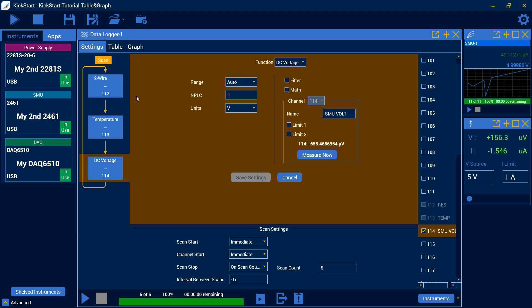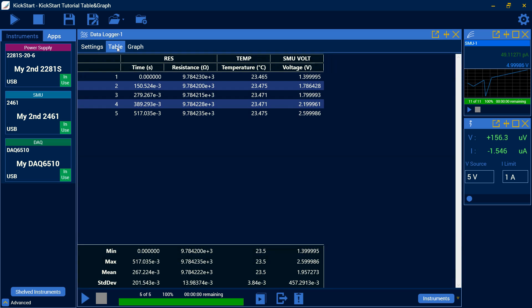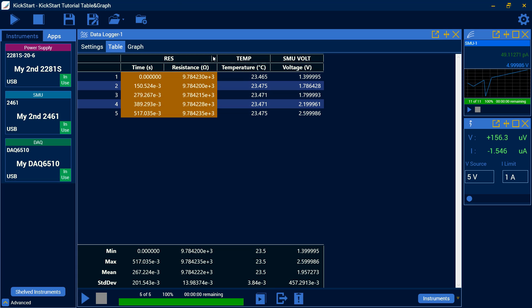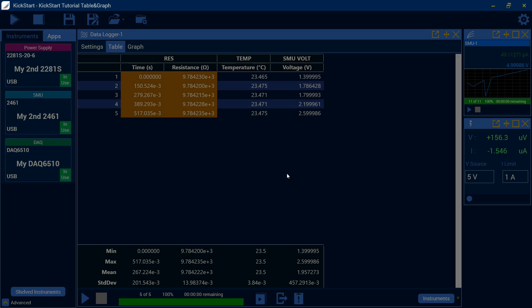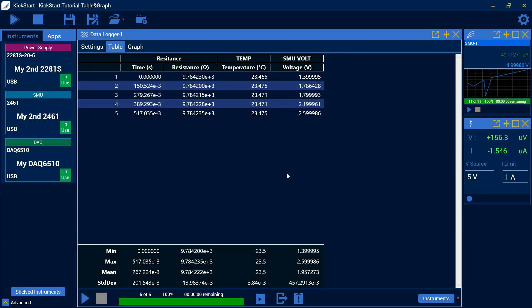We'll be able to take a look at some of our other features here. On our data logger, you can see here we're just on our settings tab, but I can also use our table view. Within the table view, I'm able to see the names for our channels. With these little drop down arrows, I can rename the channel. If I wanted this not to be res, but actually spell out resistance or some particular device, I can change the name there.